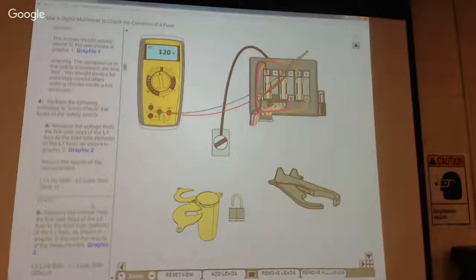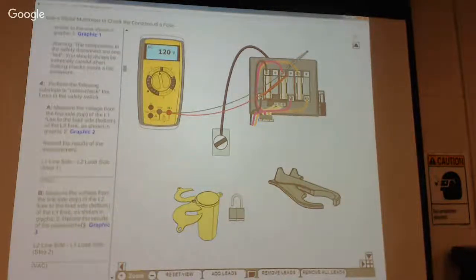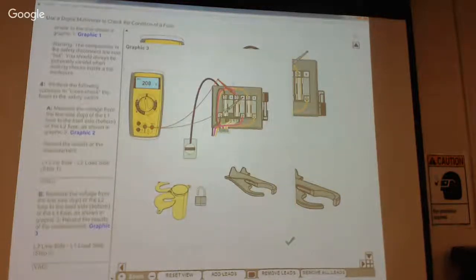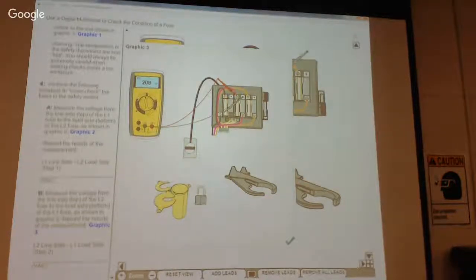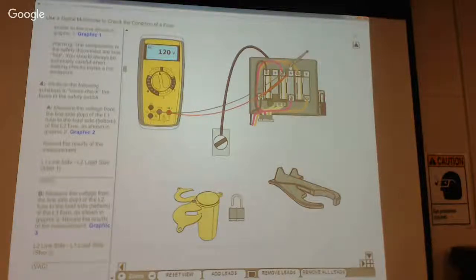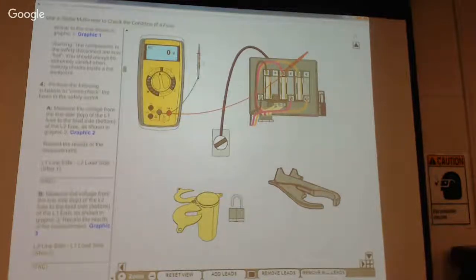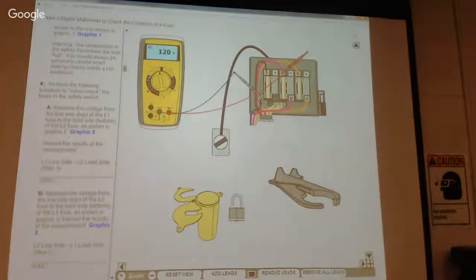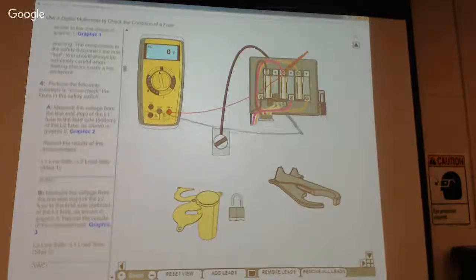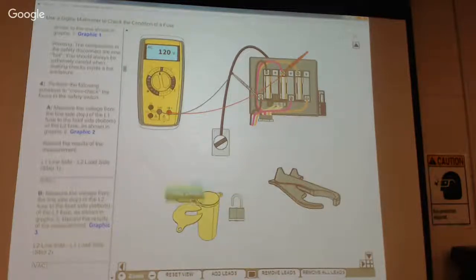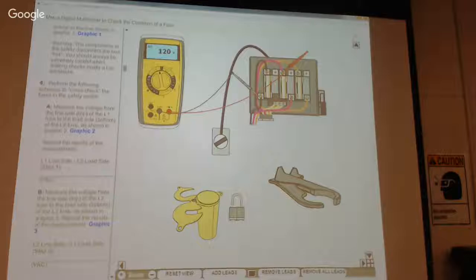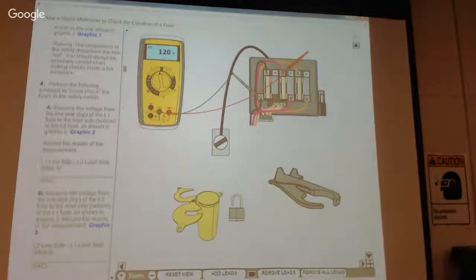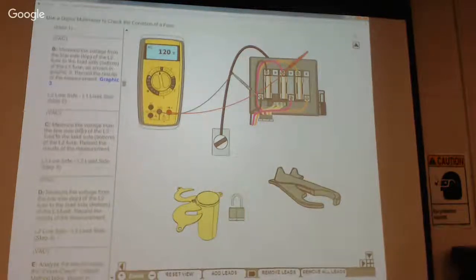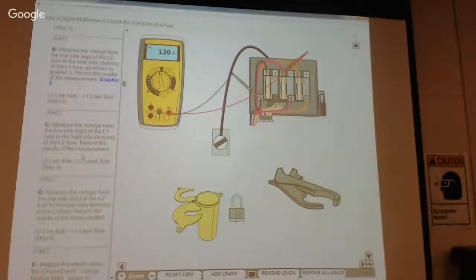All right. Measure the voltage from the line side of L2 to L3, shown in graphic 3. So look at graphic 3. They want us to go through here like this. They're actually touching on the blade here. So let's see. Let me go on there. Measure the voltage from the line side of L3, and record that. So you might have lost a phase.